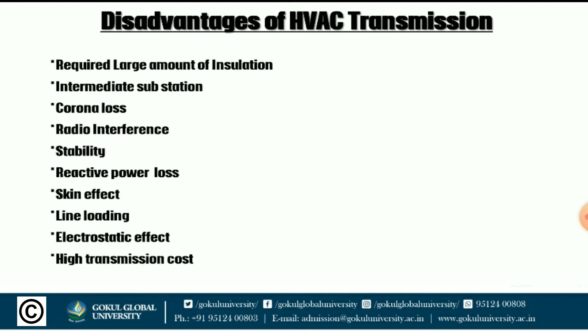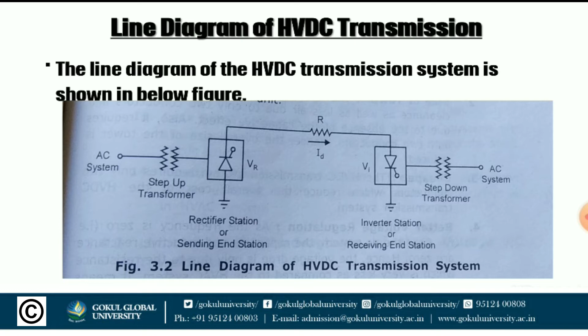Now, we discuss the line diagram of the HVDC transmission system. The line diagram of the HVDC transmission system is shown in the figure below. In the figure, we show two units. One is a rectifier section and the second is an inverter section. The rectifier station at the starting of the transmission line is called the sending end station, and the inverter at the last end is called the receiving end station. On the sending end side, a step-up transformer is used, and on the receiving end side, a step-down transformer is used.